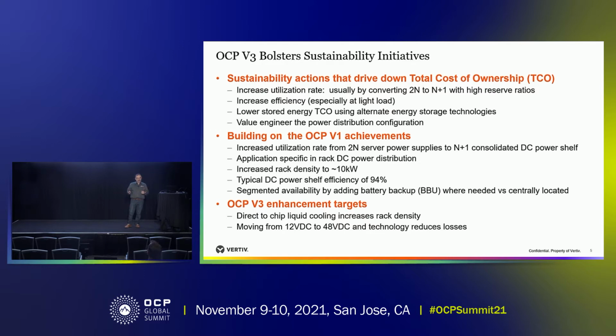So what that means is if you had a primary and a backup, now you were operating at 50% utilization. But if, let's say, you do a 7 to make 6, or a 5 to make 4 system on the power side of the business, now your utilization has increased and you've shifted the curves of efficiency. So you've automatically increased your efficiencies, reduced your losses by moving to that new structure in V1, going from 2N to N+1 on the power side.